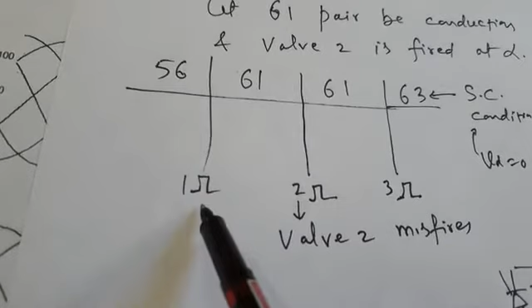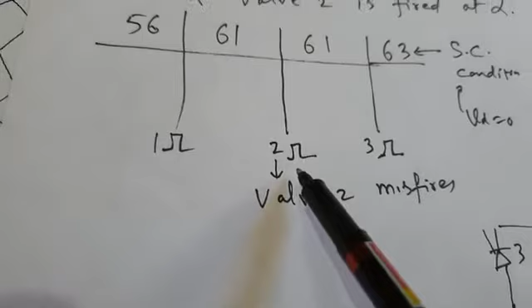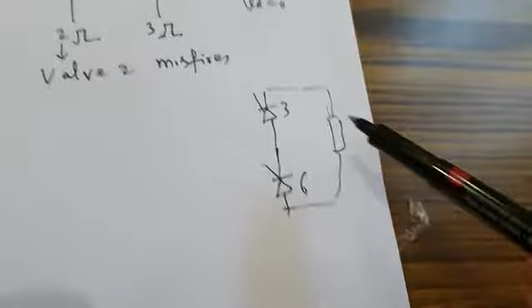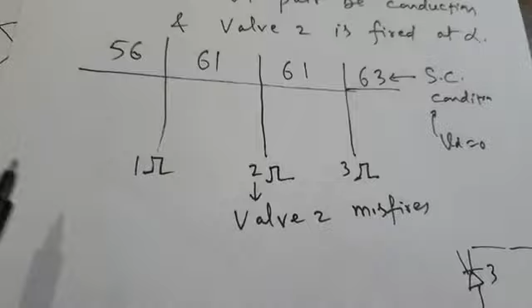Here we have assumed valve 2 misfires. We started with the conduction of the 5-6 pair. After 60 degrees, a firing pulse is issued to valve 1, so valve 1 immediately goes into conduction and the conduction changes from 5,6 to 6,1. Then after another 60 degrees, a firing pulse is issued to valve 2, but valve 2 misfires. So 6,1 will continue for the next 60 degrees because 2 has failed to fire. Then after another 60 degrees, a firing pulse is issued to valve 3, so 3 will go into conduction. Conduction will change from 6,1 to 6,3, and 6,3 is a short circuiting condition. And therefore the mal operation and the variations in the converter output voltage will take place.